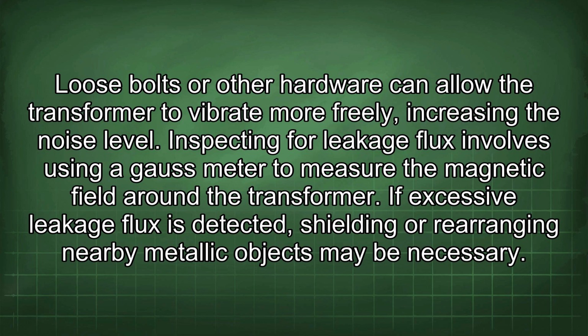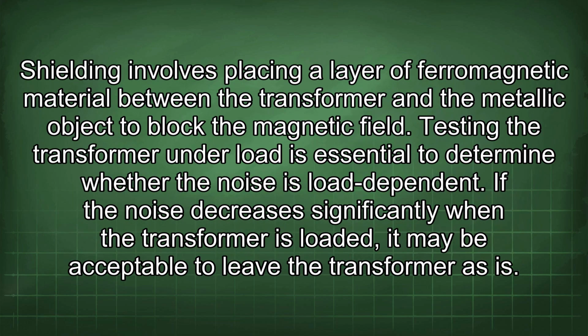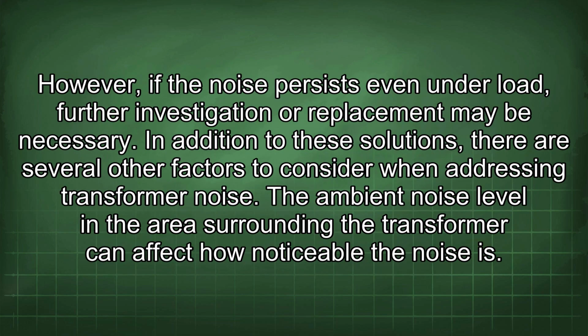Inspecting for leakage flux involves using a Gauss meter to measure the magnetic field around the transformer. If excessive leakage flux is detected, shielding or rearranging nearby metallic objects may be necessary. Shielding involves placing a layer of ferromagnetic material between the transformer and the metallic object to block the magnetic field. Testing the transformer under load is essential to determine whether the noise is load dependent. If the noise decreases significantly when the transformer is loaded, it may be acceptable to leave the transformer as is. However, if the noise persists even under load, further investigation or replacement may be necessary.